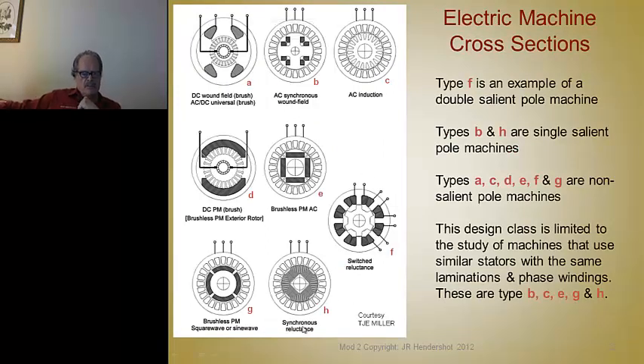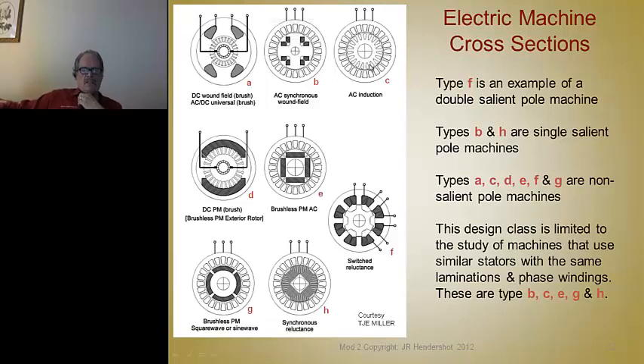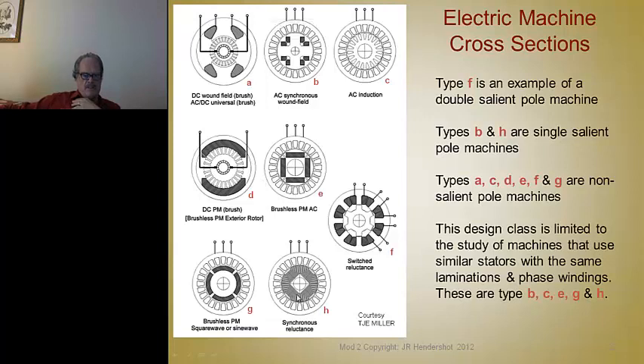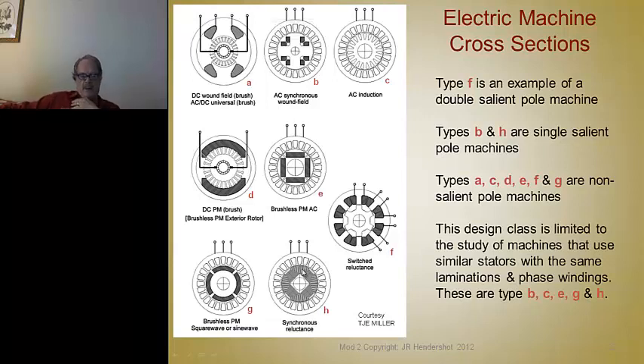The induction machine has the same stator as the other machines, but a different rotor — a punched lamination with slots filled with current-carrying conductors, either wound or cast in. The reluctance machine rotor is made up of pieces of steel and air, plastic, or magnets. The steel parts are called magnetic flux carriers; the air, plastic, or fiberglass sections are called flux barriers. If this is the direct axis, the inductance of the phase windings is high because there's a lot of iron in the circuit.